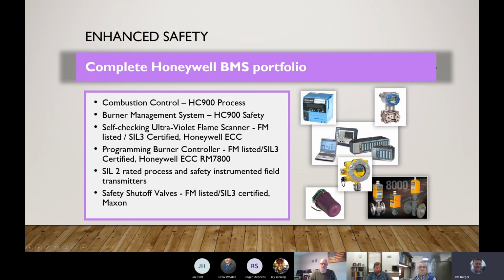You move through the next component here. This is a gas detection or gas transmitter that senses LEL, O2, a lot of different types of gases, and that also carries a SIL rating, along with a UV detector. This little purple can here is a self-checking detector, and then last but not least, the valving that would be your safety shutoff valves on the gas train. The Maxon valves can offer up to SIL 3 certification for delivering gas to the burner. So you can see that Honeywell is very serious about safety. They have a lot of components here that complement the HC900 system that can be offered in a package to accomplish higher levels of safety out in the plant and the process area.